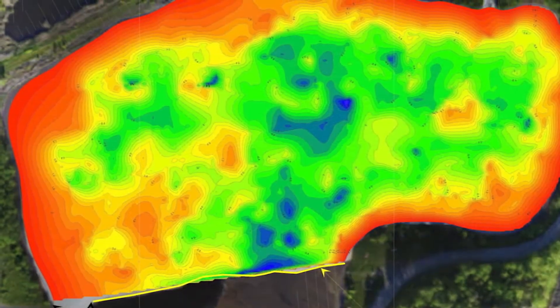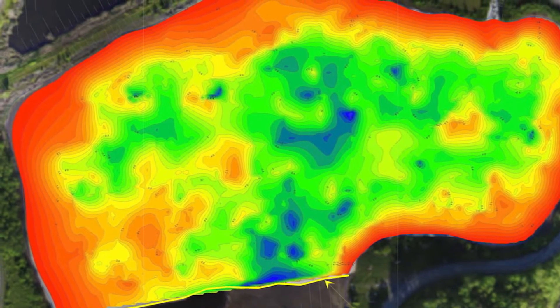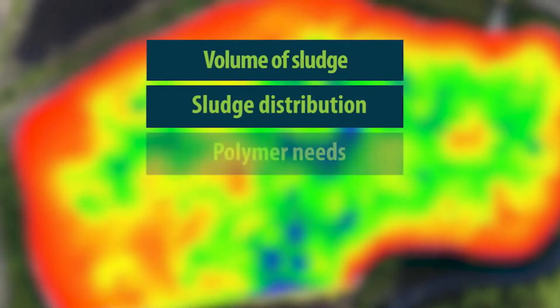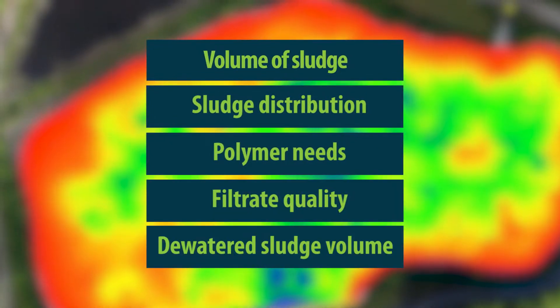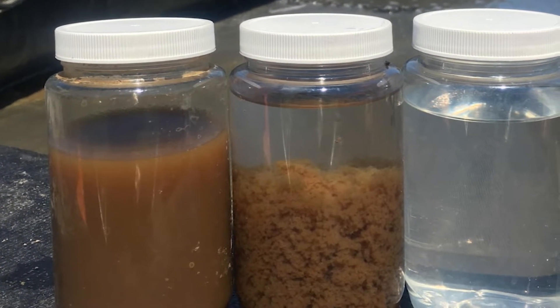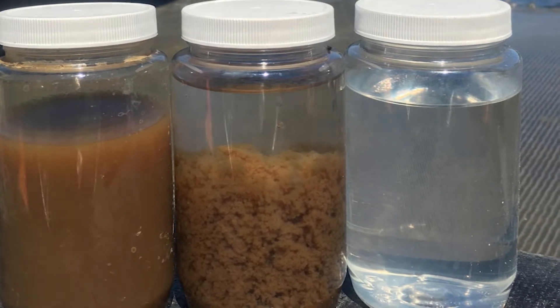Each lagoon clean-out starts with a sludge survey and sludge dewaterability testing. These help determine important parameters like the volume of sludge in the lagoon, how it is distributed, the best polymer for sludge dewatering and solids retention, the filtrate quality, and the dewatered sludge volume. Our sludge testing also identifies contaminants of concern, such as metals, which can affect how the sludge is disposed of or repurposed.